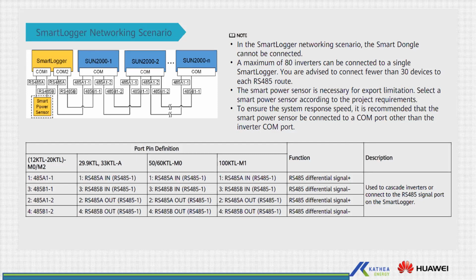If you are using one of the inverters as master, it means all your inverters will be daisy chained on RS485A1, all the inverters up until the master inverter, which is the first inverter. And then your meter, you wire it on RS485A2. That's where you wire your meter on RS485A2, and then we'll look into tomorrow how to configure the meter on the inverter.